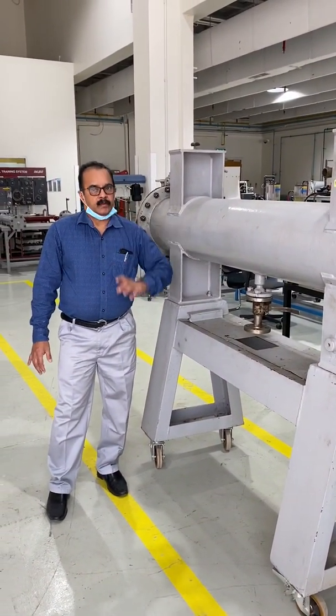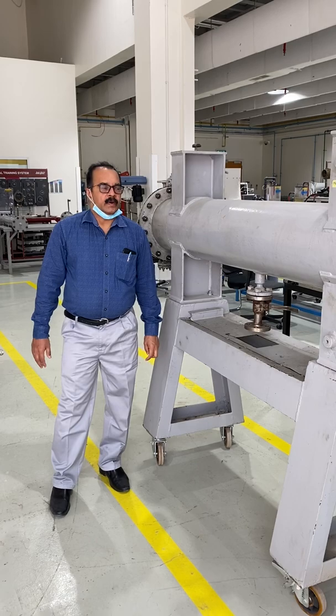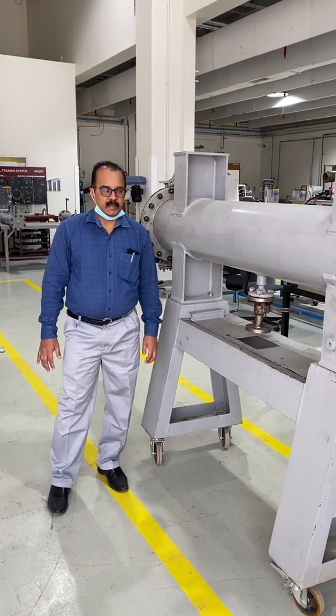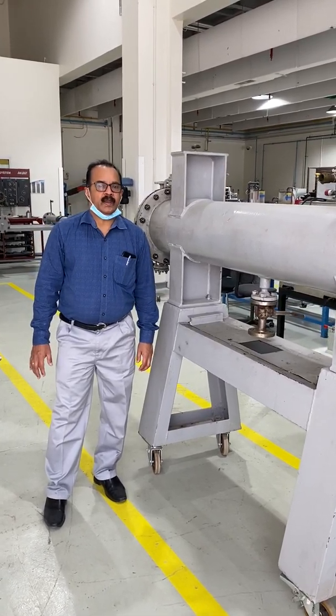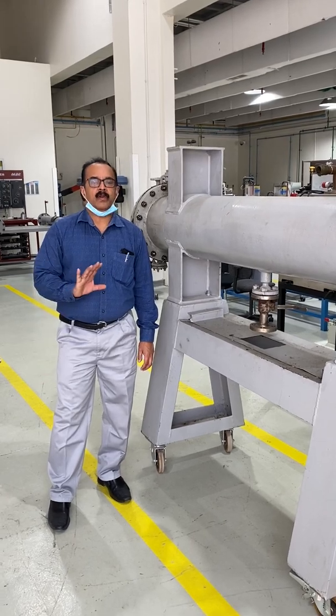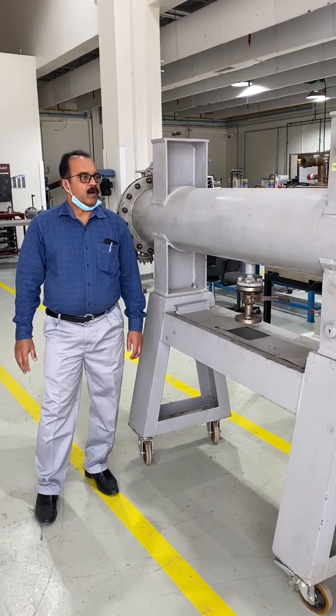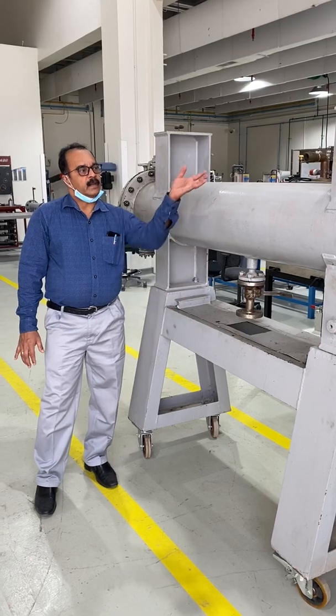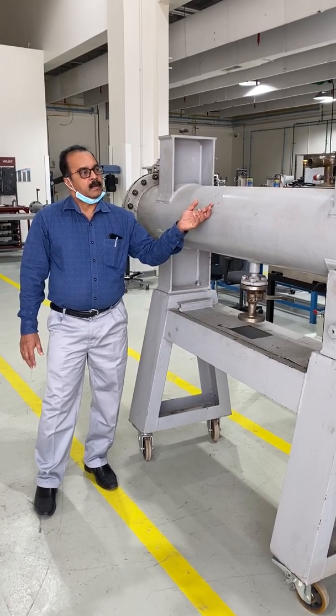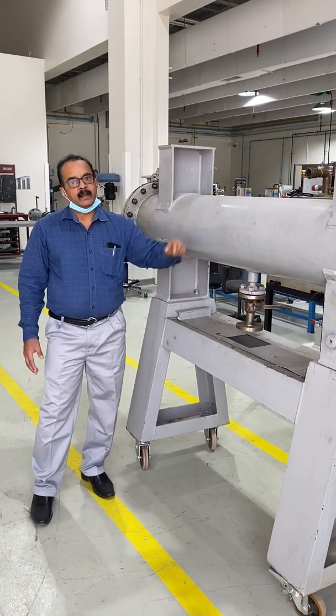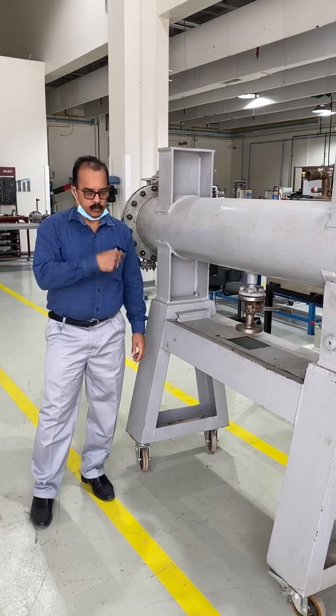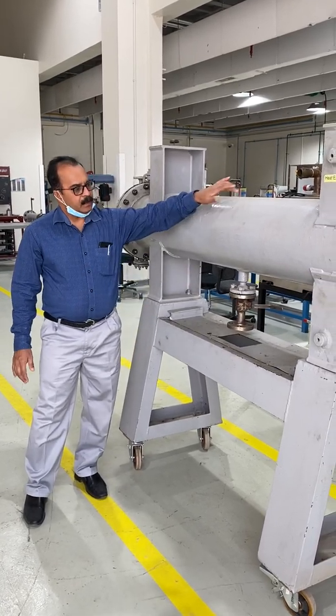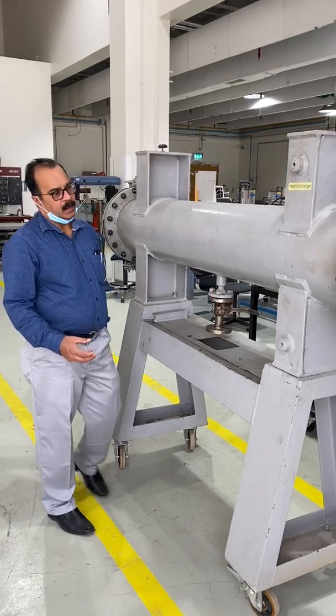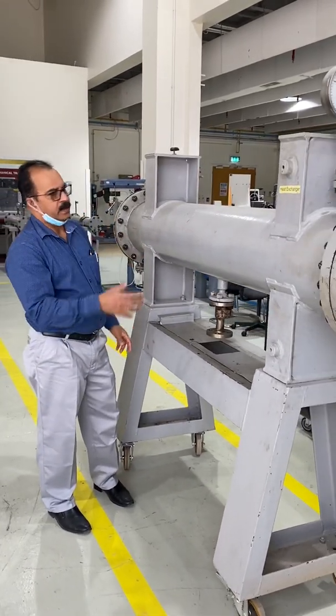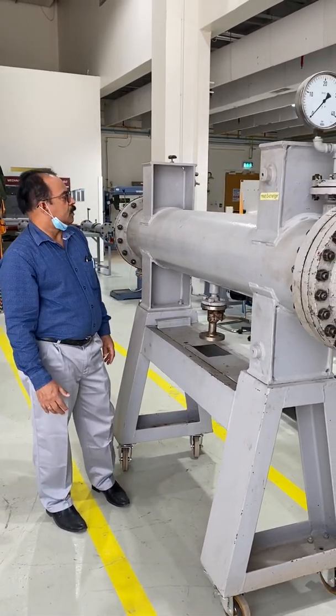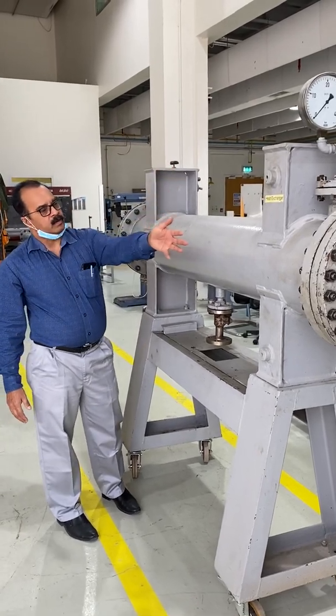A shell and tube heat exchanger is an exchanger where the fluids will not mix. That is the specialty of any heat exchanger: the hot fluid and cold fluid will not mix. The hot fluid will be inside the shell, and the cold fluid will go through the tubes. So this is the shell, and inside you can see there is a tube bundle. There are a lot of tubes inside. I cannot open this; you need a crane for it, it is very heavy.